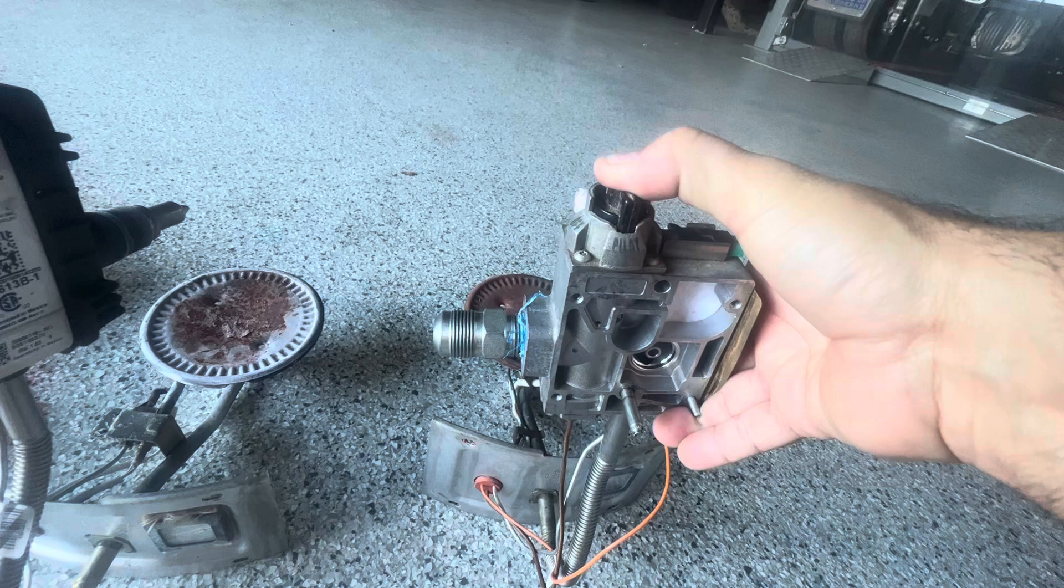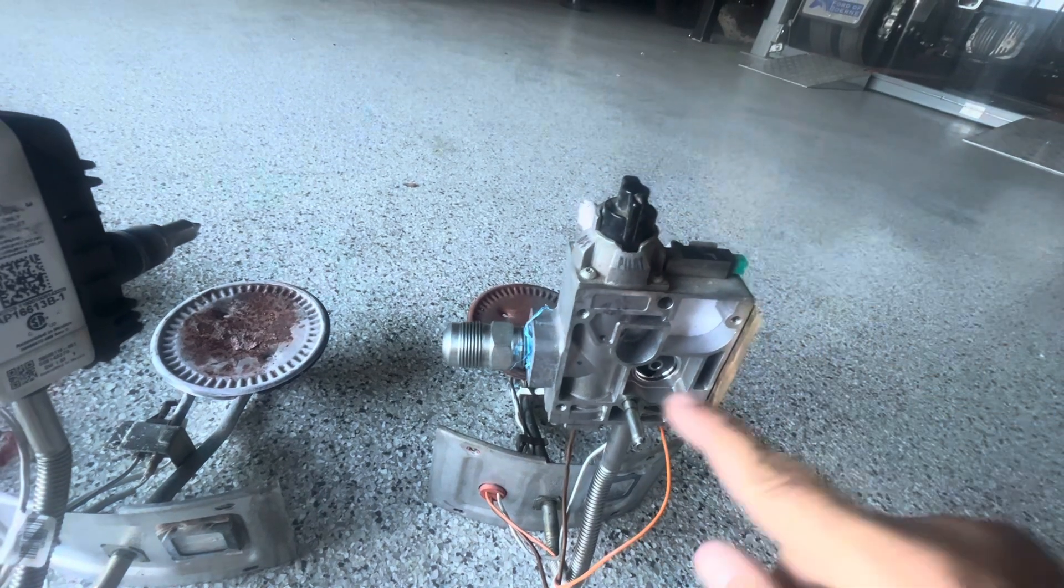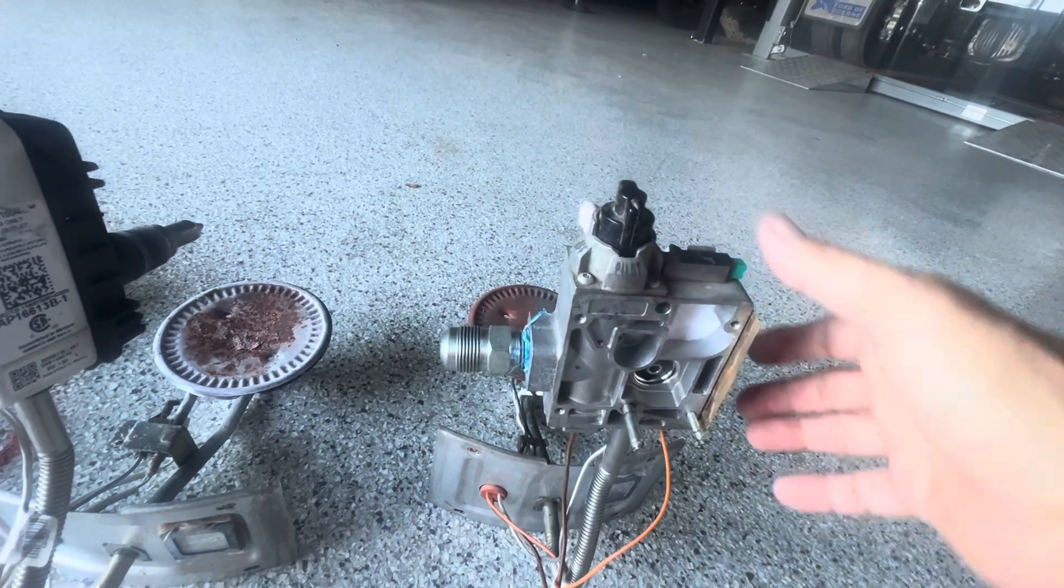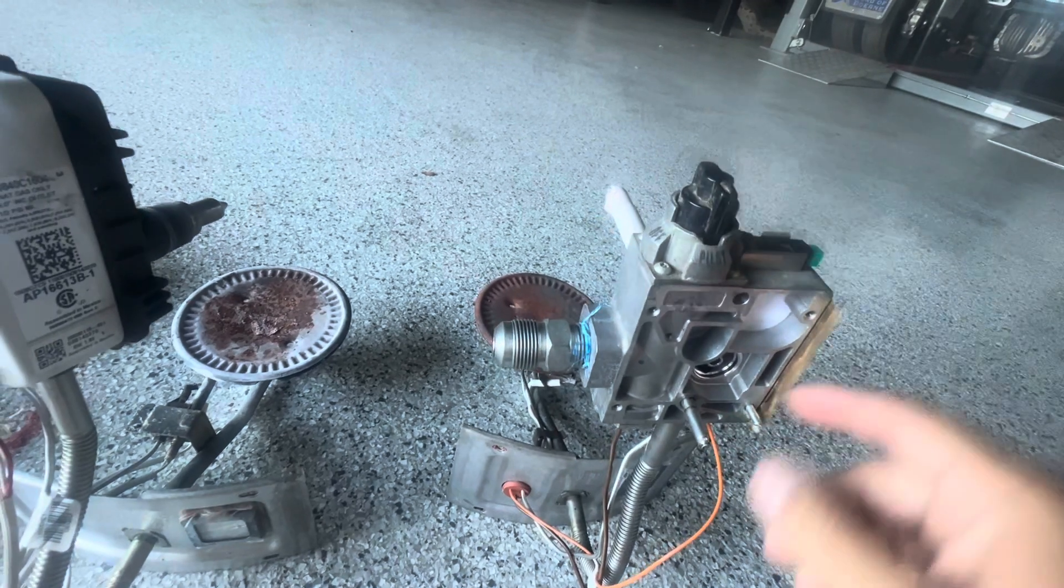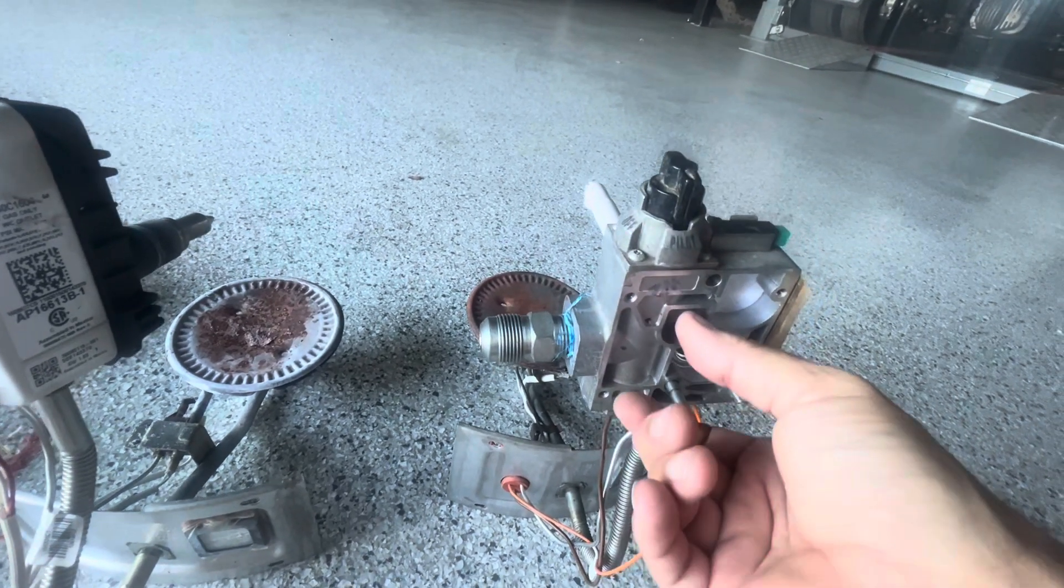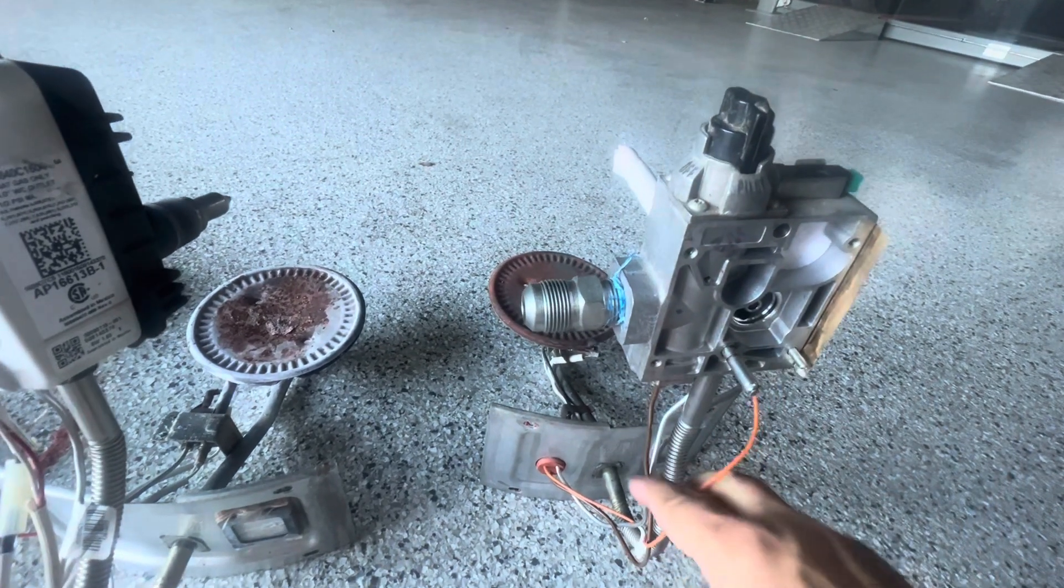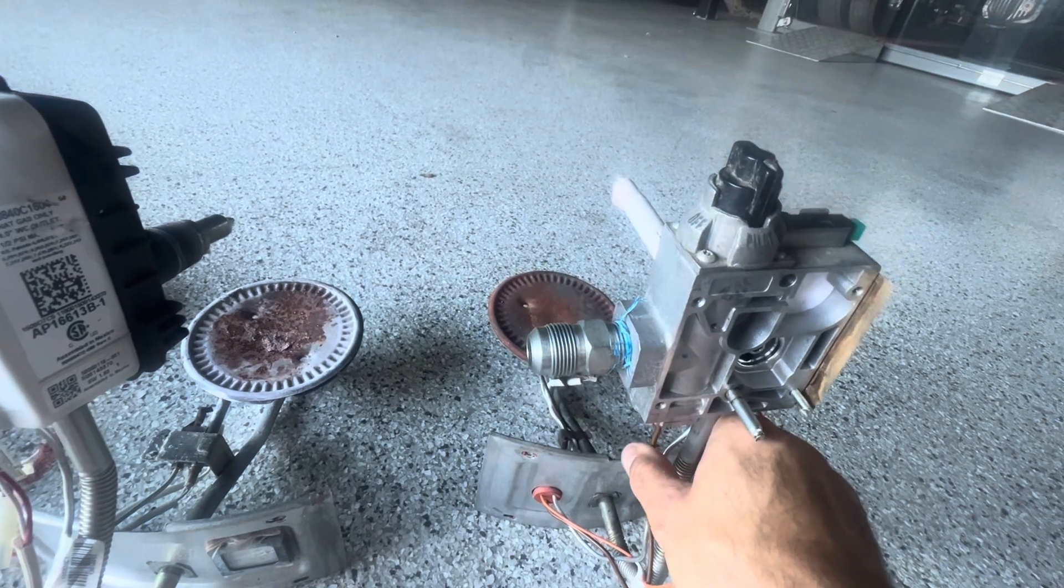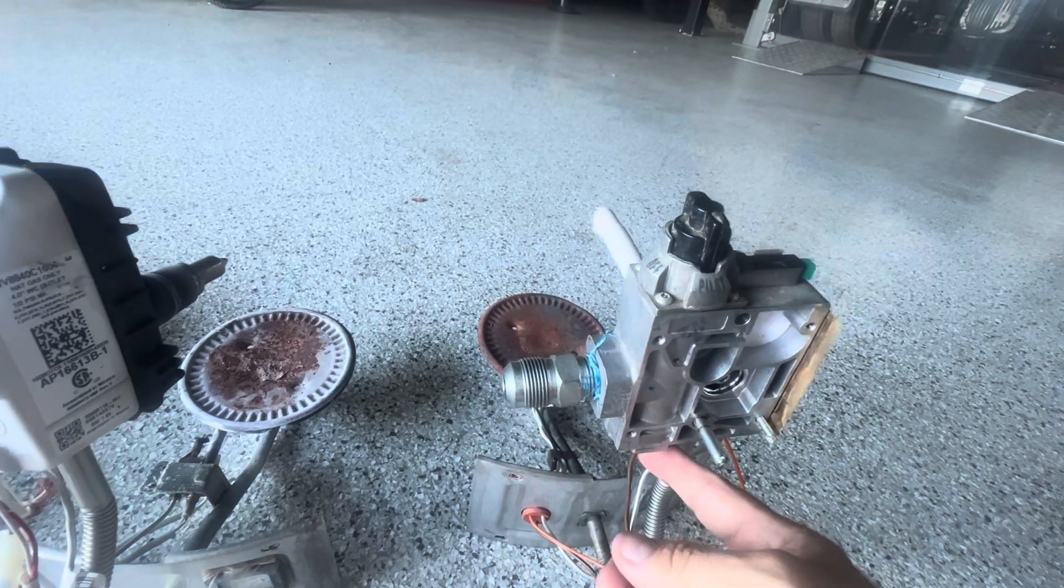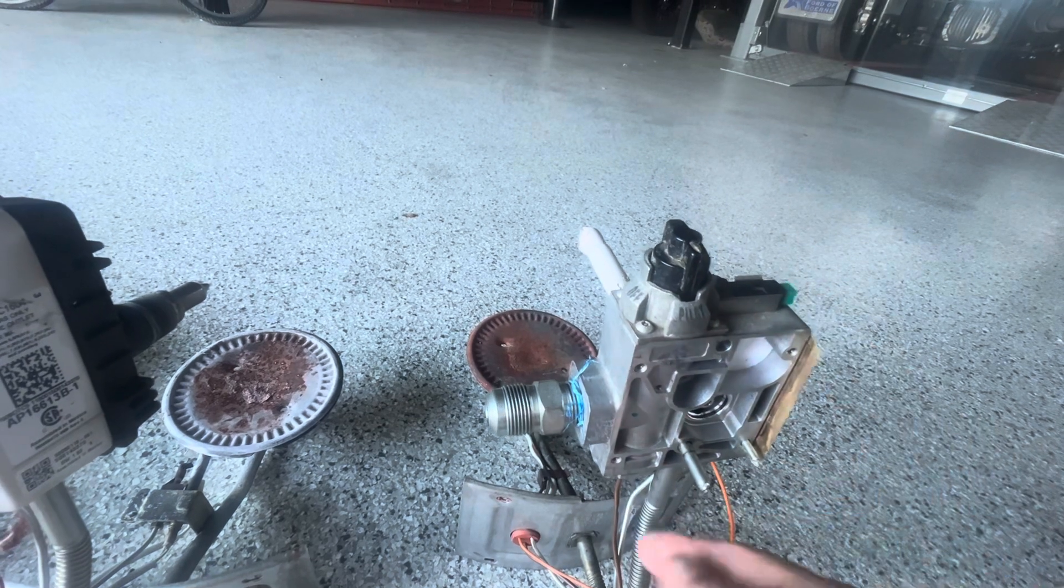When you press this down, you will open up the line for the gas to go through and down to the pilot tube. Once this mag assembly in here gets enough magnetic charge, magnetic field from the thermocouple or millivolts, I should say, it creates that magnetic field.